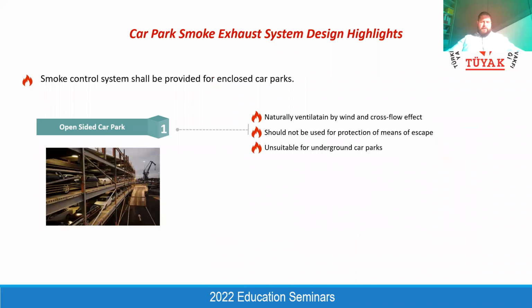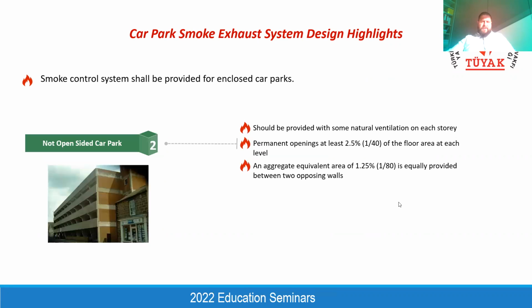And also, as the last issue, if we have a car park, and we always have a car park for the high-rise building within the downtown of the cities for sure, we need to provide a smoke exhaust system as well. For the open car parks, the smoke exhaust system is not required, but to consider a car park as an open car park, there should be at least 2.5% of the sectional area of each floor on the facade. For example, if you have a floor with 100 square meter, there should be 2.5 square meter opening on opposite facades of the building.